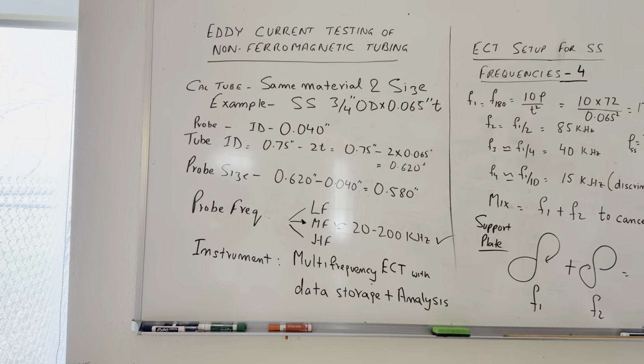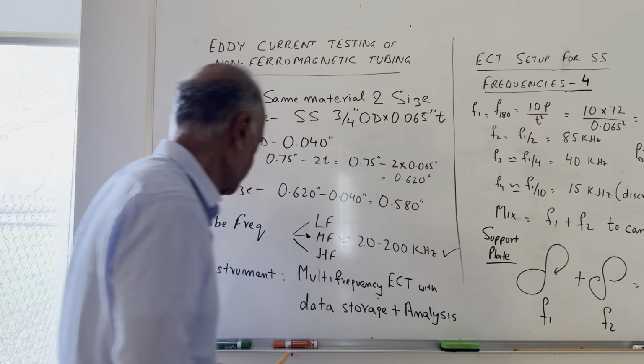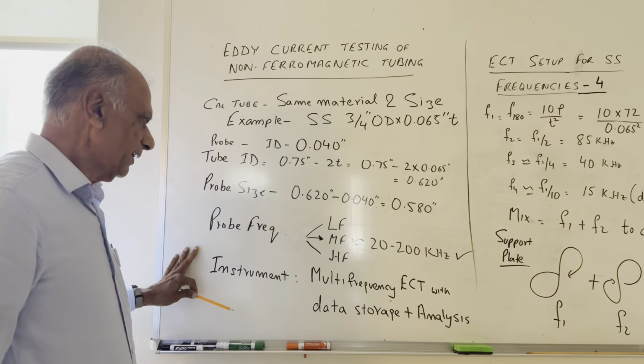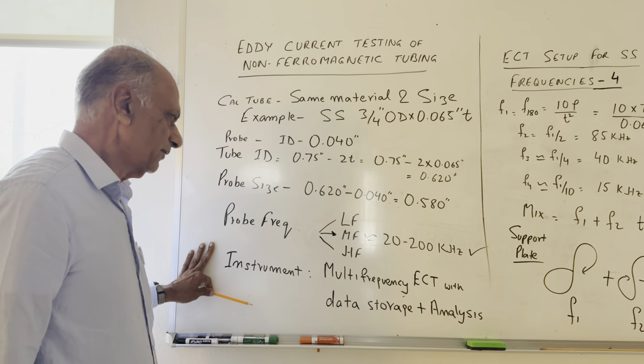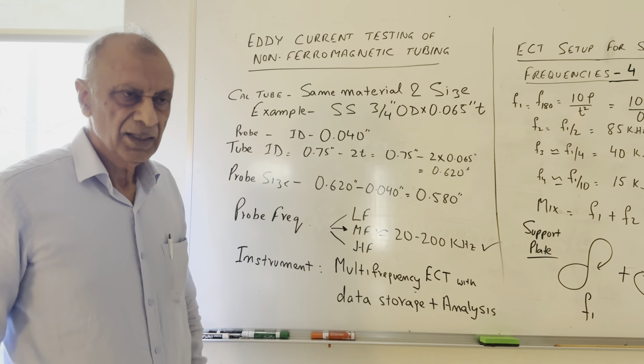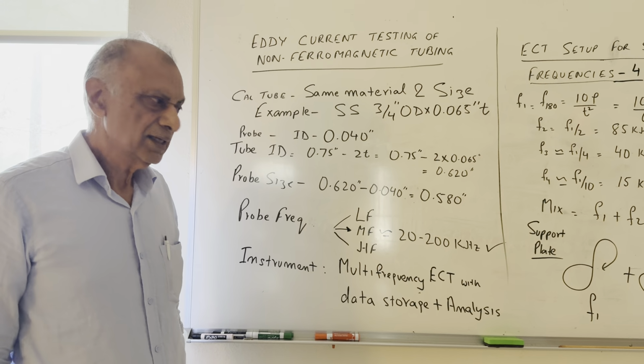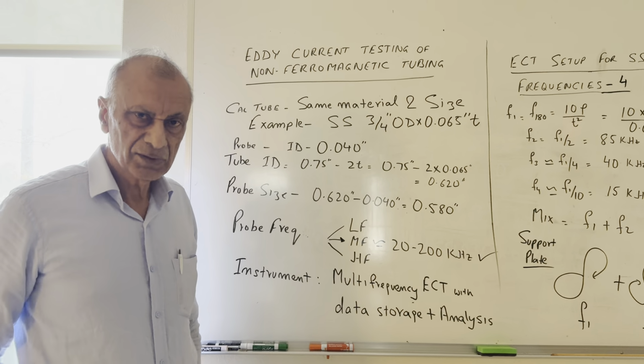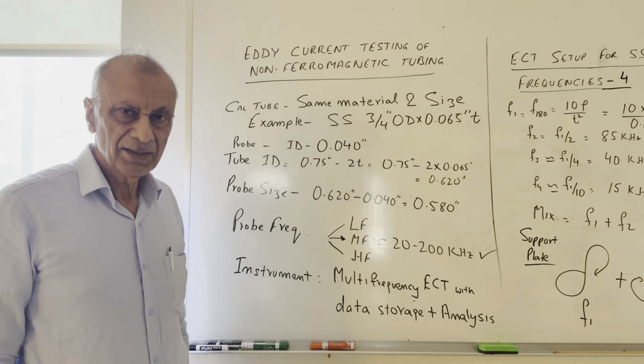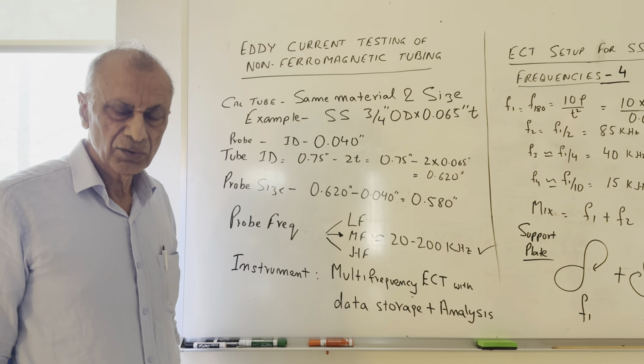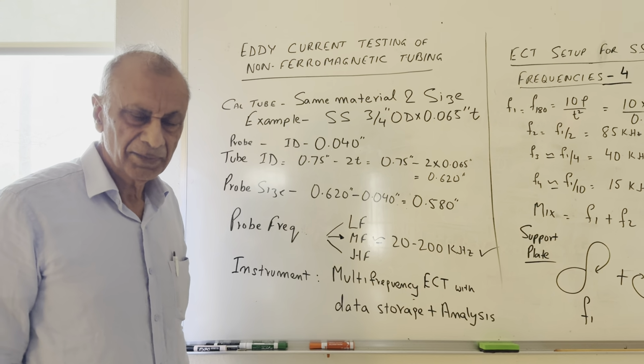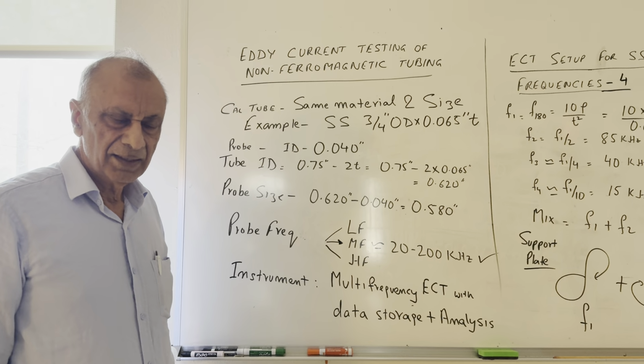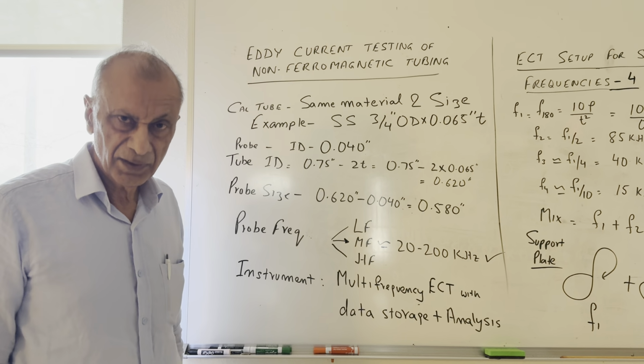Now we have the probe, and the next thing is that the instrument has to be special. These are multi-frequency ECT machines which have 4 frequencies, and they have the capability to save the data and also do the analysis to calculate the depth of the indications based on the depth curve.